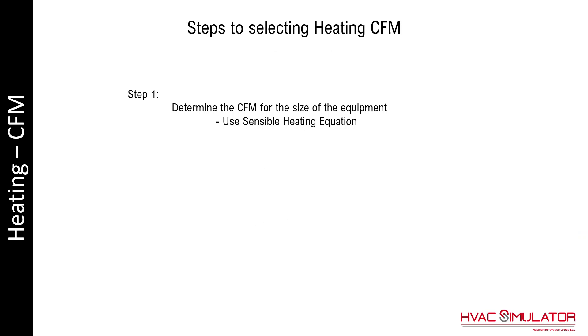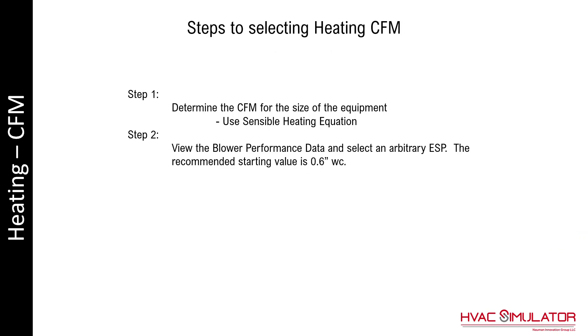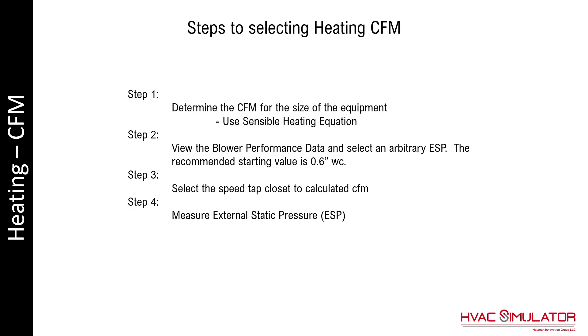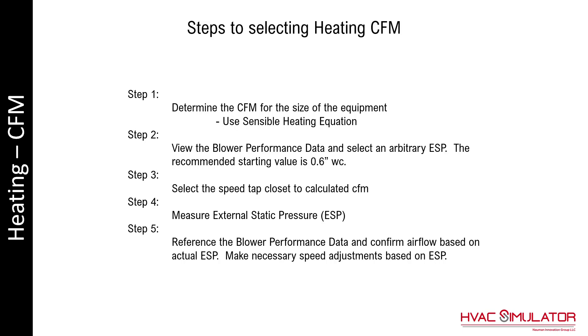Just like cooling, there are steps to selecting heating CFM. Step 1 is to determine the CFM using the sensible heat equation — 639 CFM for a 40,000 BTU furnace. View the blower performance data and select an arbitrary ESP; the recommended starting value is 0.6 inches of water column. Select the speed tap closest to the calculated CFM. Measure the external static pressure, then reference the blower performance data and confirm airflow, making necessary adjustments based on external static pressure.